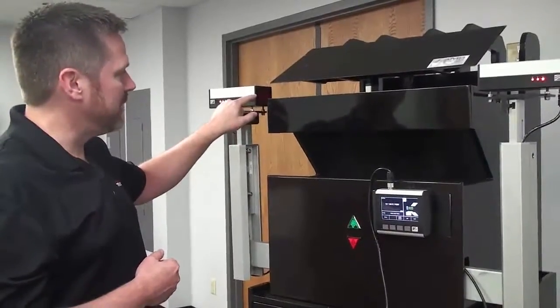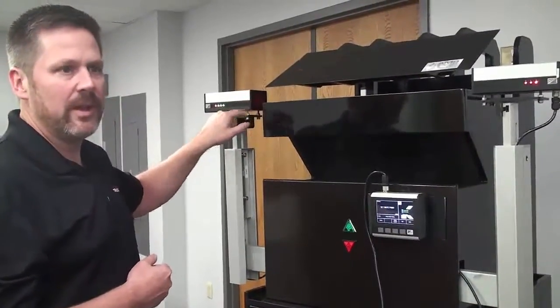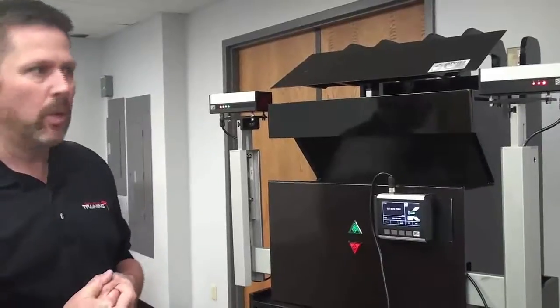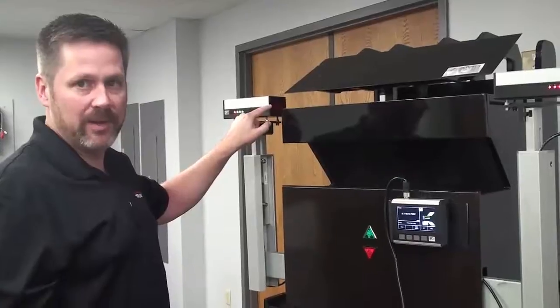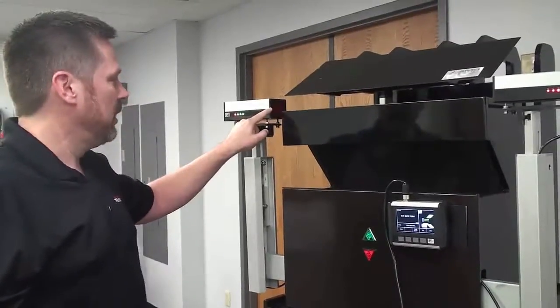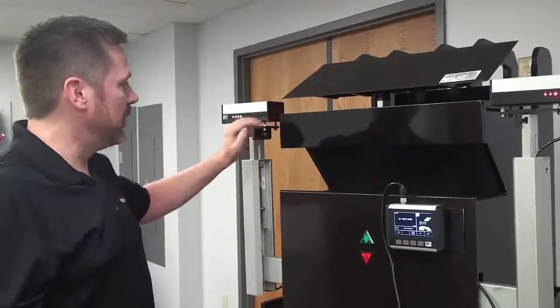Actually, what happens is 2 millimeters plus or minus these lasers, it will mute itself. So you do lose protection of this laser 2 millimeters above and below each laser.